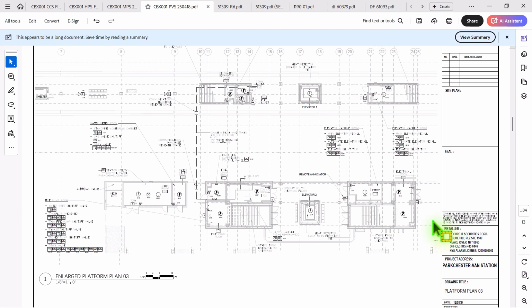In the direction of the remote annunciator, that's the only location getting 4 wires, because 2 wires go for the remote annunciator, for communication and 24-volt power — so 116 and 114. The 116 runs for the data for the smoke detectors and heat detectors in that area, and the other 14 is for the outputs, the horns and strobes. Keep in mind, if there are any relays in that area, we'd need to either continue from the remote annunciator or pull a separate circuit for the 24 volts. You'll see what I mean when I go over the drawings.